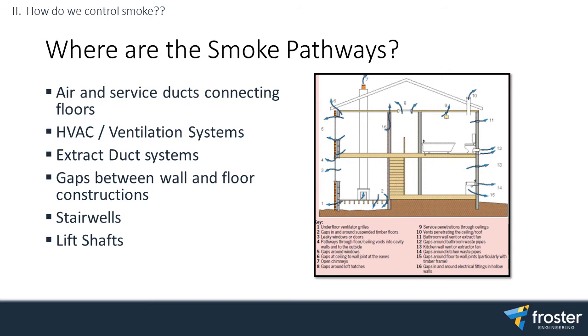If we're running air through a building, we have to ensure we know where the fire compartments are and how we protect one zone from another using fire dampers, smoke dampers, and smoke control. Obviously, HVAC systems themselves, either exhaust or air conditioning systems, are going to contribute to transferring smoke around the building. Exhaust systems, same thing. Also have to be mindful of gaps between walls and floors of construction that will transfer smoke. So we can do our job. The contractor can make sure everything's airtight, dampers are installed correctly, but if the builder hasn't done his job, then that's going to compromise the entire system, isn't it? To some level. So just showing where all the risks are. They're everywhere. So everyone needs to be aware of it.